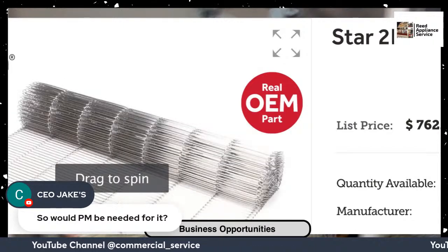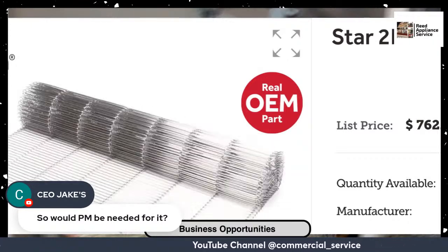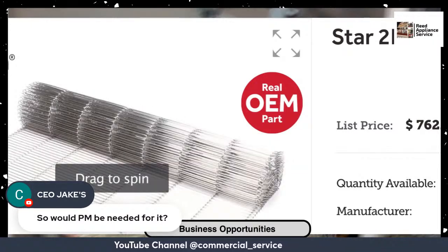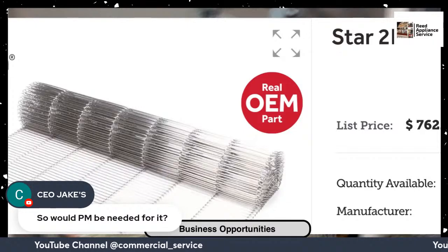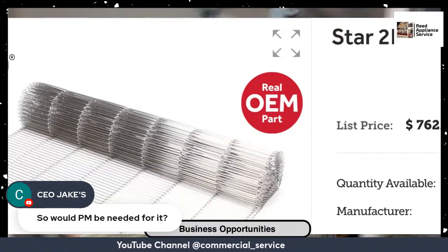That is up to you. It all depends on how busy the store is, because how busy the store is determines how much heat is going to be inflicted upon that belt. It's not going to make it to a PM. Chances are, if it's a big, fast moving store, they're just going to wreck the belt.